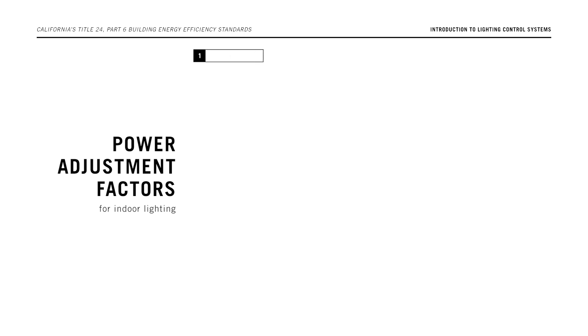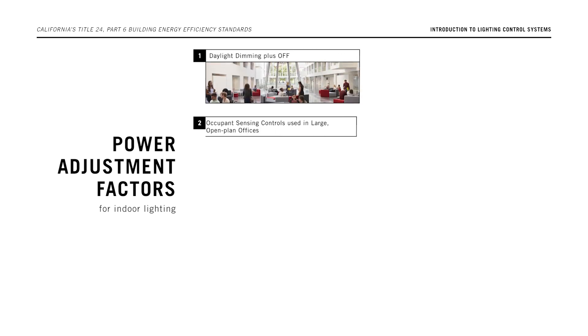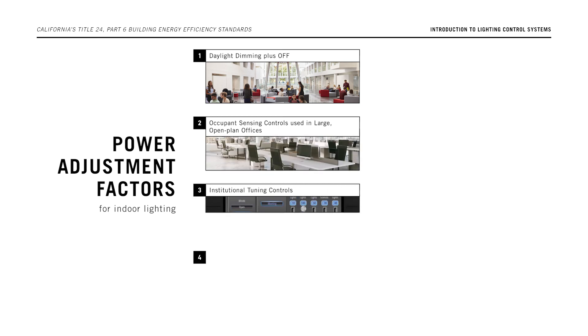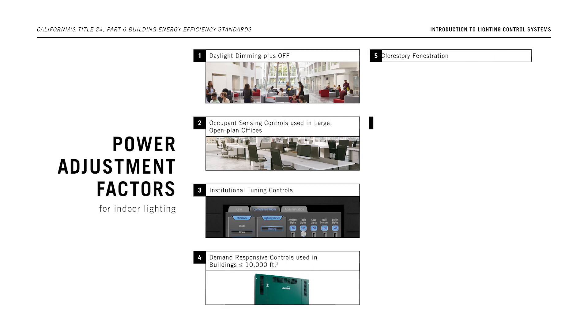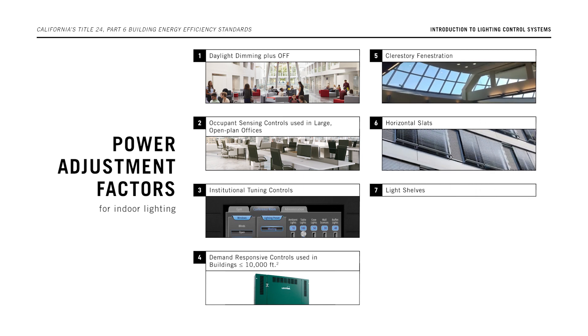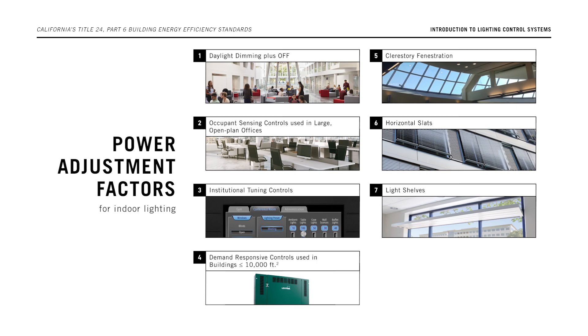Power adjustment factors are available for seven specific control measures which go beyond the Energy Code's mandatory measures. They include daylight dimming plus off, occupant sensing controls used in large open plan offices, institutional tuning controls, demand responsive controls used in buildings 10,000 square feet or less, clerestory fenestration, horizontal slats, and light shelves. You can find more information on these control strategies in section 140.6 of the Energy Code.